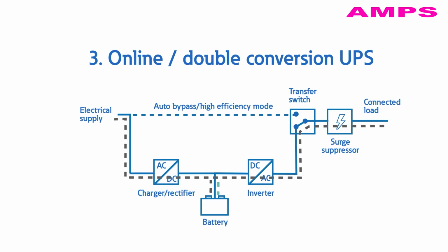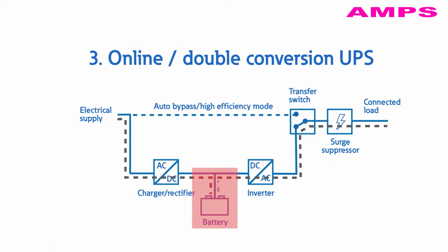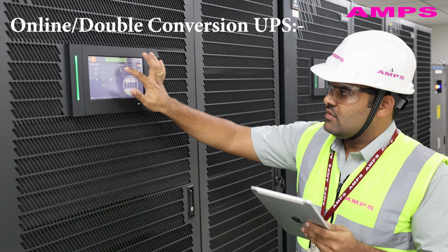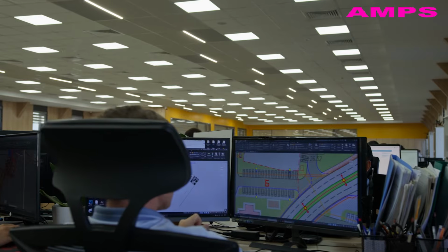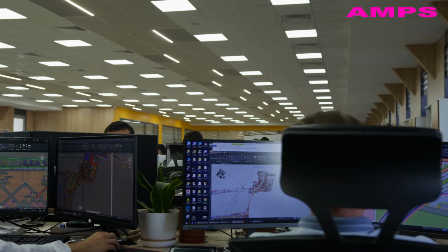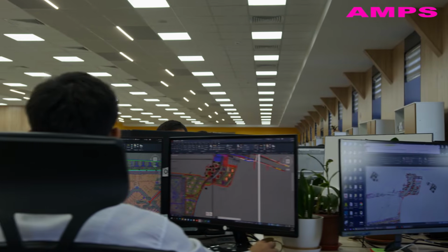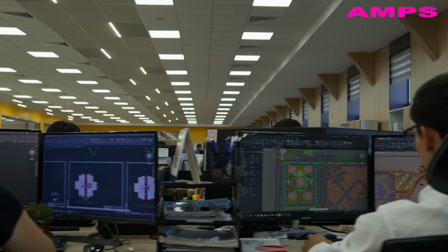3. Online or double conversion uninterruptible power supply. The online or double conversion UPS differs from the offline or standby as the DC to AC inverter is always connected on. This means there will be no transfer time between the main power source and battery, providing greater protection against spikes, sags, electrical noise, and complete power failure. Online UPS is the most reliable and offers the best protection, making them ideal for motor applications or situations where you can't afford any transfer time. Best uses are for software, corporate companies' computers, servers, data centers, or intensive care units.